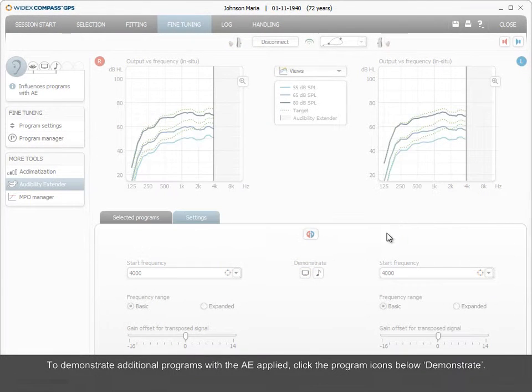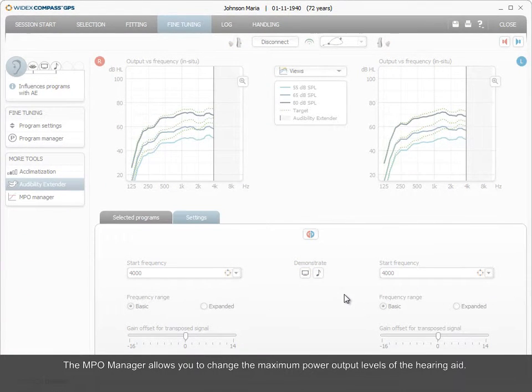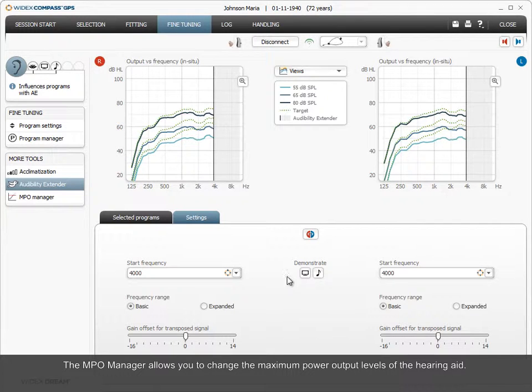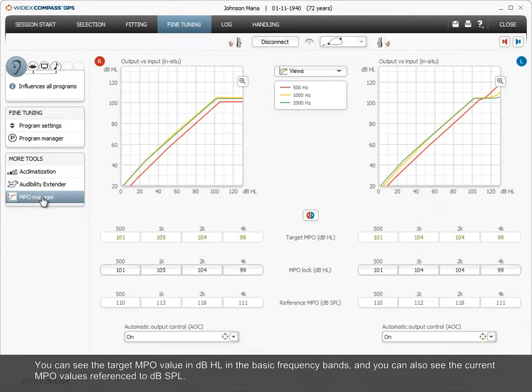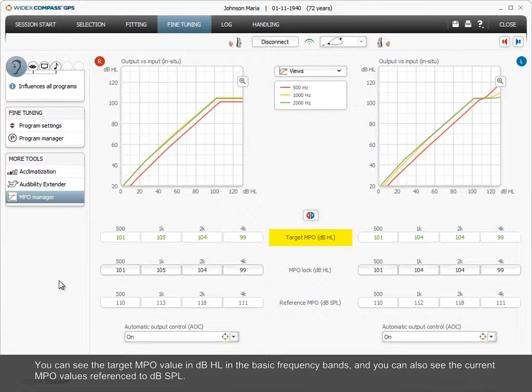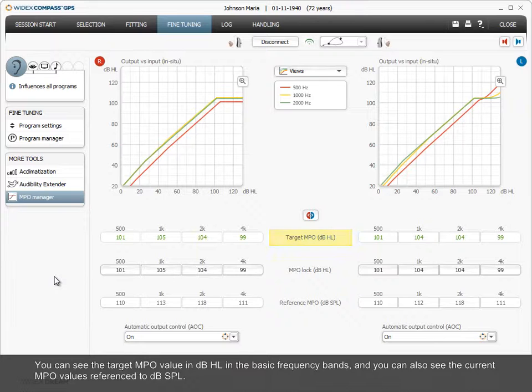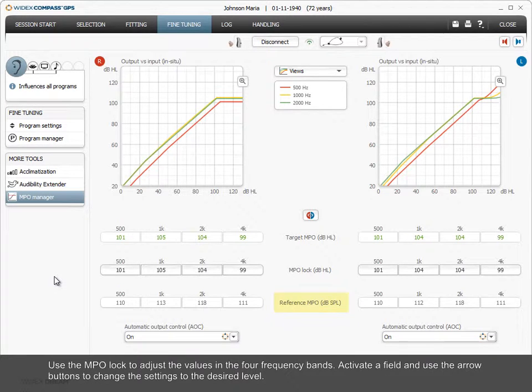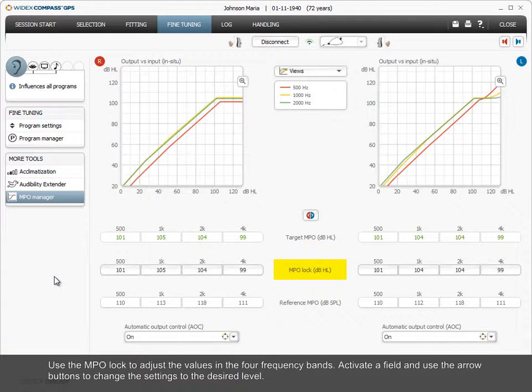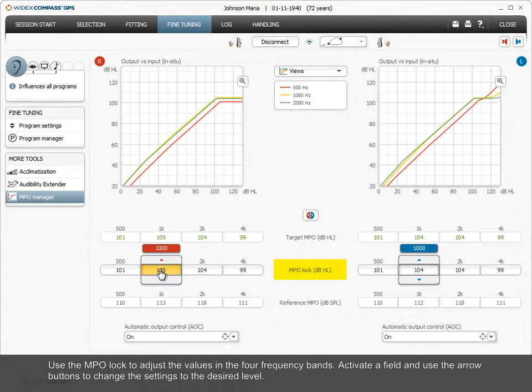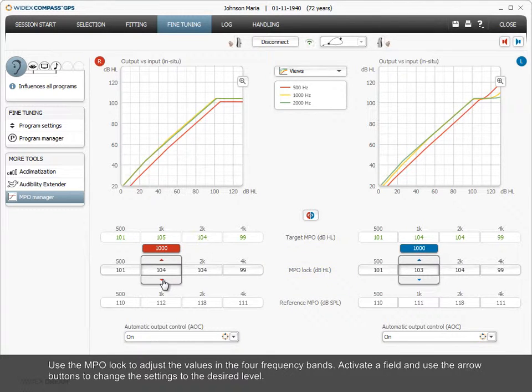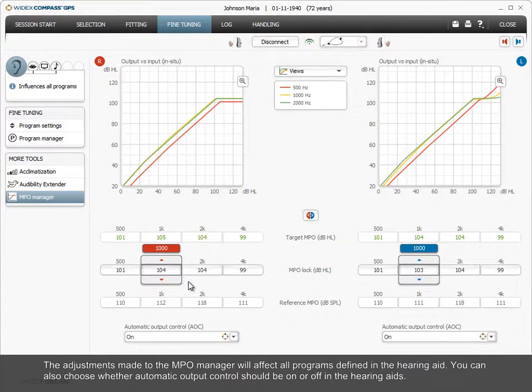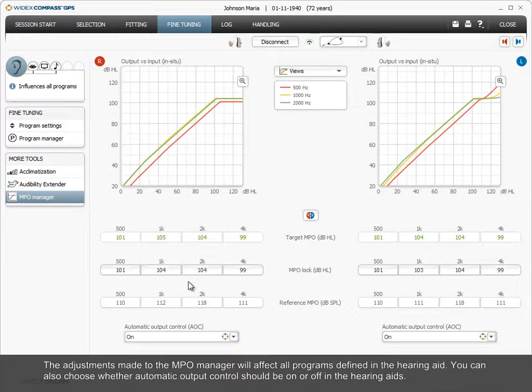The MPO Manager allows you to change the maximum power output levels of the hearing aid. You can see the target MPO value in dB HL in the basic frequency bands, and you can also see the current MPO values referenced to dB SPL. Use the MPO lock to adjust the values in the four frequency bands. Activate a field and use the arrow buttons to change the settings to the desired level. The adjustments made to the MPO manager will affect all programs defined in the hearing aid.